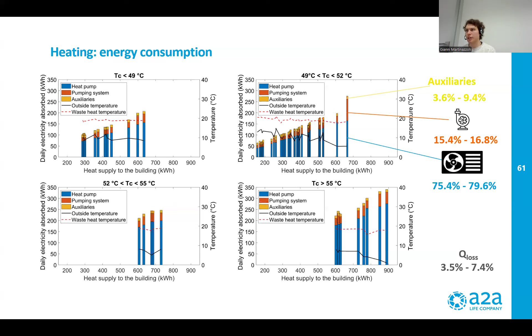You can see also the percentage of electricity consumption for each component, and you can see how the consumption of the pumping system is not negligible. This is one of the main features of this kind of network, where the temperature difference between the supply and return line is reduced, and so the flow rate of the network increases a lot compared to a conventional network.